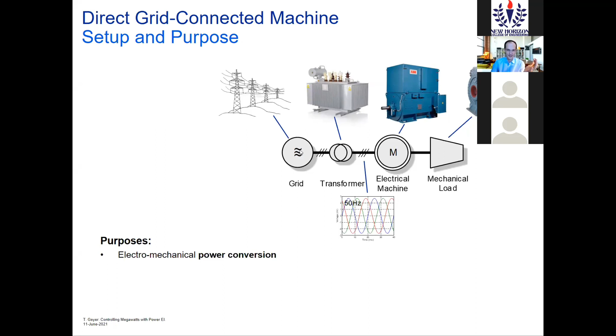But if you would like to control the speed of your load, then you need to decouple the machine electrically from the grid. And you do this by adding a variable speed drive. So you go from 50 Hertz, from AC to DC with a rectifier. It could be a passive rectifier like a diode front end, or an active rectifier using semiconductor switches. And then you go from DC to AC, but now you can choose your fundamental frequency. And maybe you can set it in a range of 0 to 100 Hertz, maybe also slightly higher. So this gives you variable speed operation.